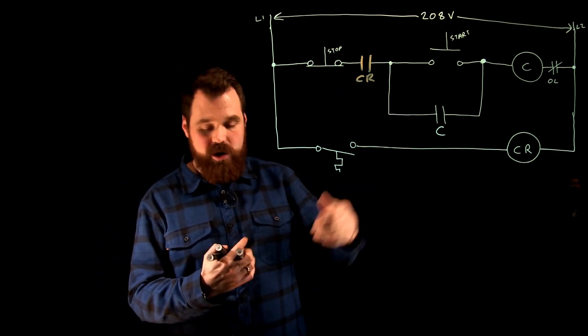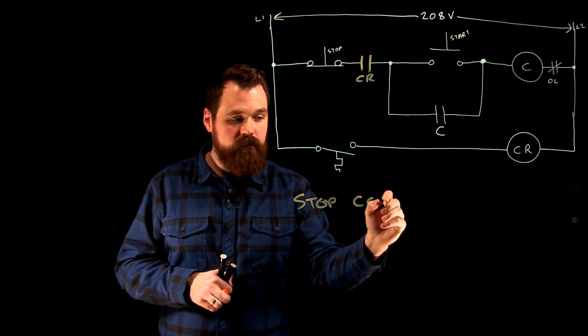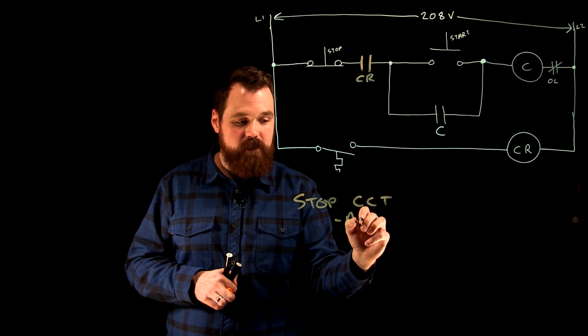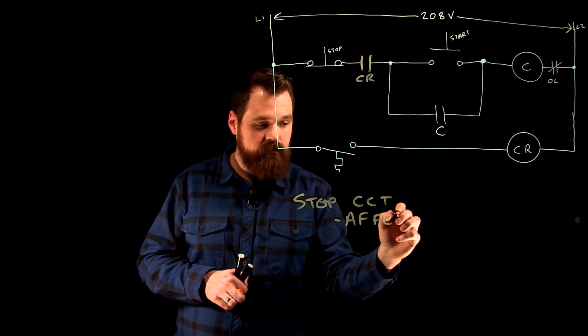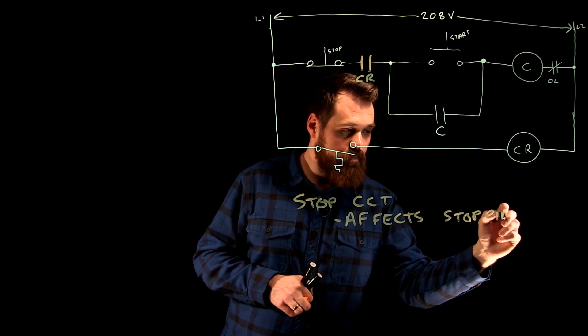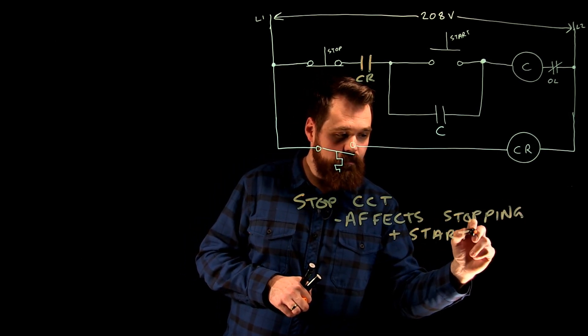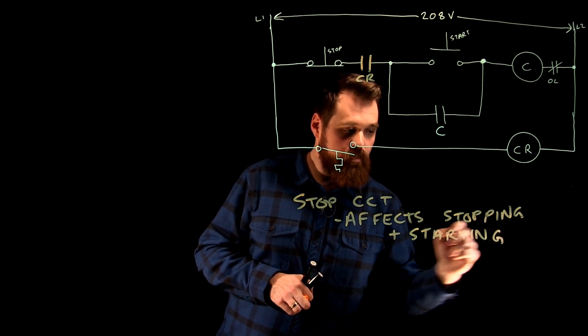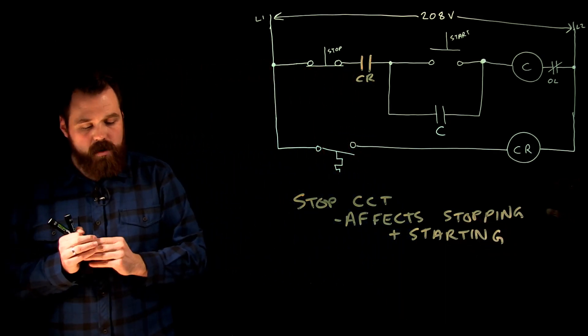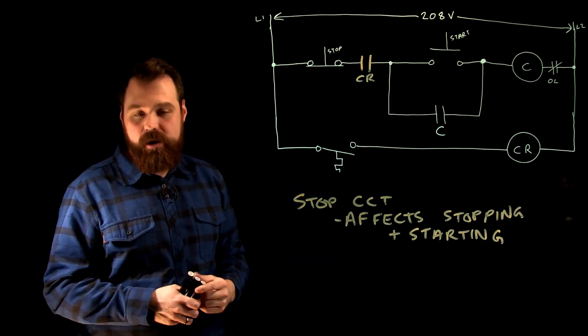When this is open, I cannot start the motor. So anything in my stop circuit, it affects the stopping plus the starting of the motor. So usually that's going to be safety devices. Opens up, motor cannot run.